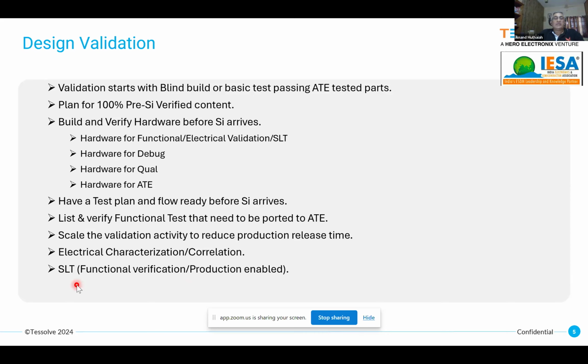That means you take a part that is already tested on the tester and found to be good, and you make it go through a functional test in production - meaning every device has to go through this. When you do a validation check earlier, you're only doing it on a few first article silicon or a few SKUs, not on every part that goes to the customer. But with SLT, every part that goes to the customer needs to be tested as a functional verification.